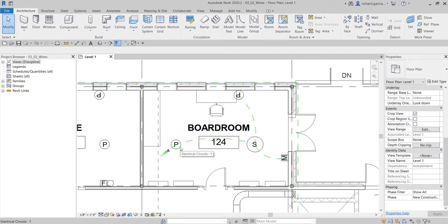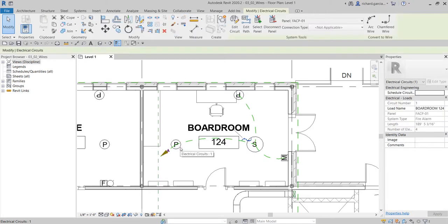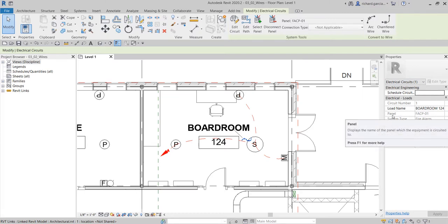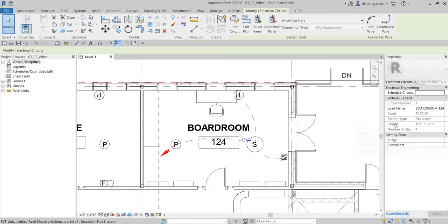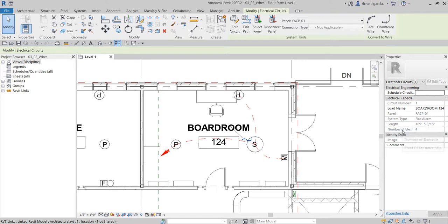Once you press tab, you can see here the preview of the wiring. Go ahead and click that. Once you click that, you will see here the circuit number, the load name, the panel where this circuit is assigned, the system type, as well as the length and also the number of elements, which is four.